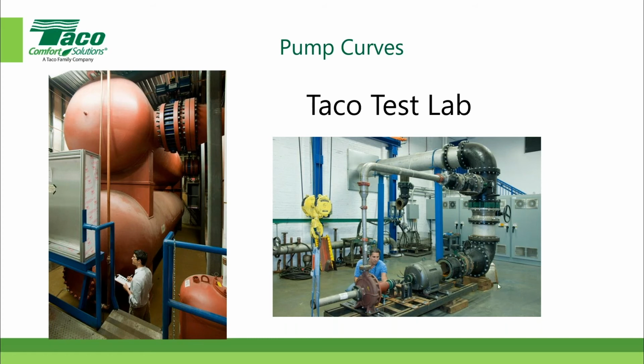If you'll notice, the electric motor down here is not connected to the pump yet, and that's because the technician will eventually connect the device which will connect the motor shaft and the pump shaft with a device called a torque cell. It'll fit right in there. And that torque cell allows us to measure the shaft horsepower, the input power to the pump. Then we're going to measure the pressure at the suction somewhere here on this pipe. And then on the discharge, we'll measure the pressure up here on this pipe.